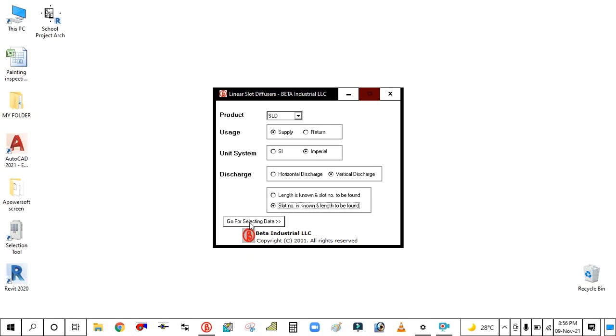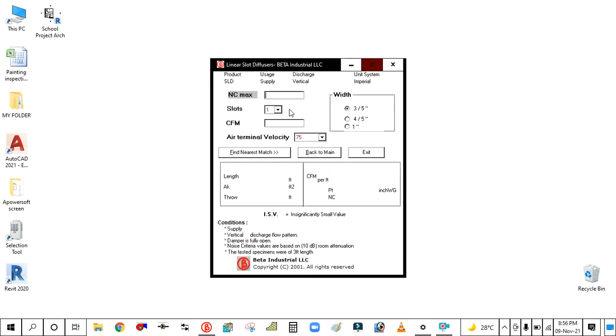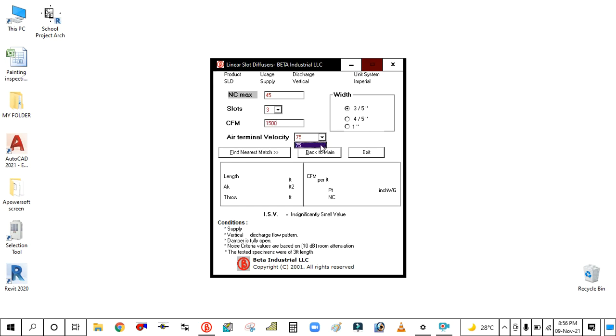Simply click here and go for selecting data. Noise criteria will be 45, number of slots is 3, CFM is 1500. Terminal velocity is 75, width is 1 inch. Simply click here find the nearest match.